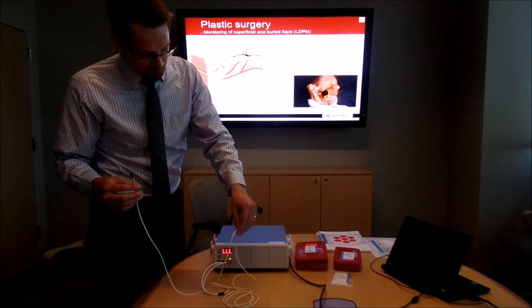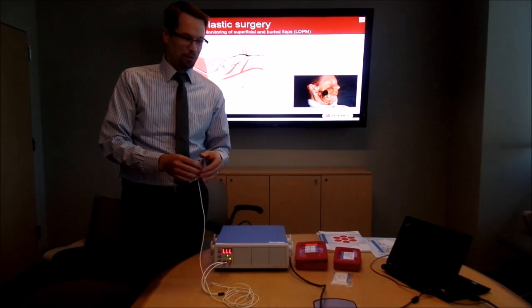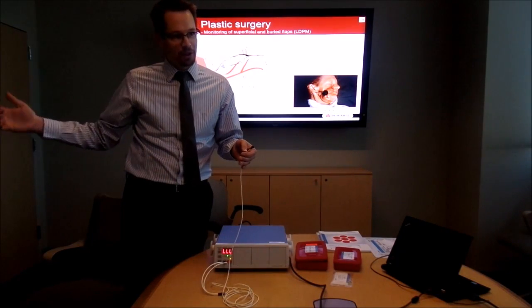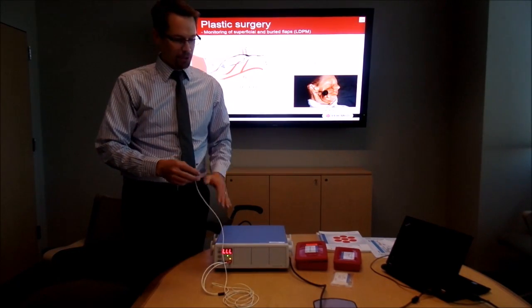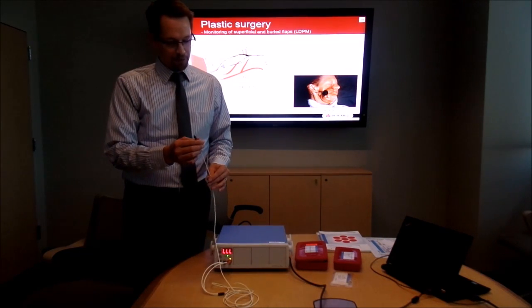But what often helps as far as keeping your probe serviceable for years to come is to ensure that the cable always stays out of harm's way, never gets caught in any closing drawers, never gets down on the ground where somebody might stumble or run over it. So keeping the cable out of harm's way is key for longevity of the probe.